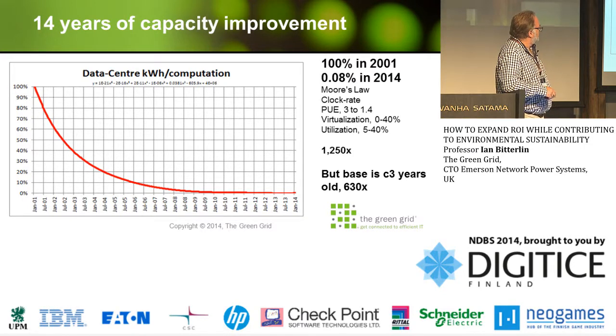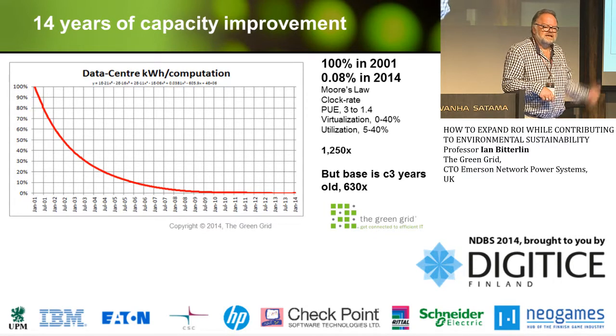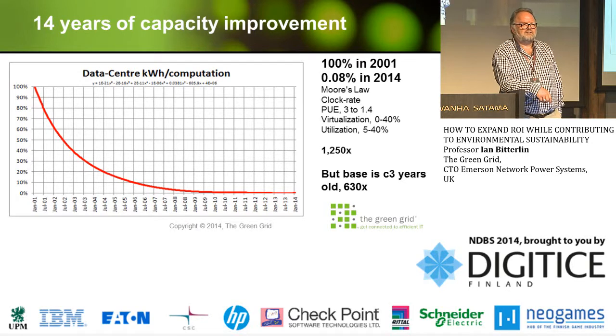But if you do the curve, you get a 1,250 times increase in capacity. Before comparing the two, think what that means: in 14 years, if we built a 5,000 cabinet, 5 megawatt data center in 2001 at 1 kilowatt per cabinet, the same computing capacity can now be carried out by less than 1 cabinet. That shows where the technology's gone - something governments, especially the EU, aren't prepared to consider. They think the data center industry is power-hungry, greedy, rapacious and dirty, ignoring that we've turned 5 megawatts into 5 kilowatts in 14 years.